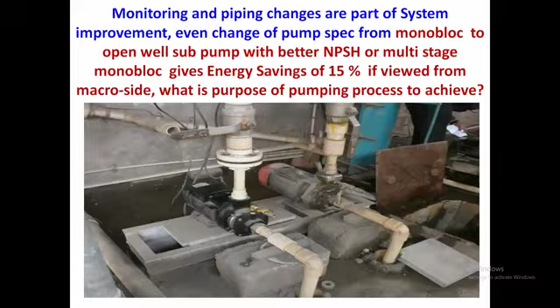First, let us measure the pump delivery, what the pump nameplate says, and what the delivered water is at the overhead tank in our college or in any of the premises, where we stand, what the difference is and how to address it. These are small pet projects you can take up. And going from a single monoblock to a multi monoblock gives another savings of around 15%, to maintain the NPSH, net positive suction head, using multi-stage monoblock pumps.